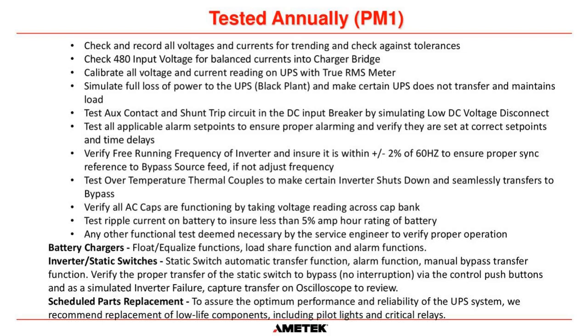We'll find that very easily by checking the current. The other thing we do, when we check the voltage and currents on the UPS, we are then calibrating them to either the analog or the digital meters. We're not just taking the readings, we're making sure that the meters on that UPS reflect the actual value that is being seen by the UPS.